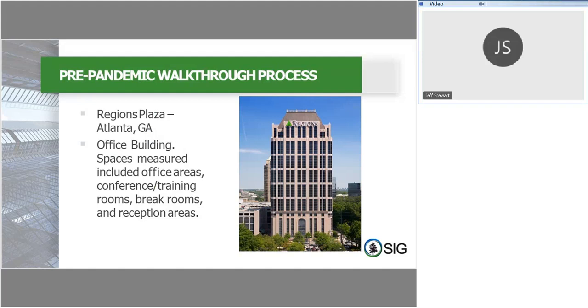And we did find a couple of rooms where the temperature was slightly above the deadband that we were looking for, and with a little further investigation, the terminal unit serving those specific rooms just needed to be adjusted to make sure that the proper airflow was coming through. Once we confirmed with the building team that those were done, we were able to submit the application, and they received their Energy Star label.